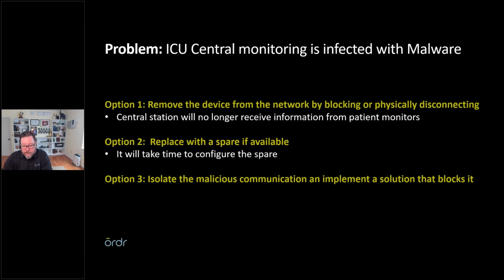Replace it with a spare if available, and that's a great solution, except I don't know if you've ever had to configure one of these devices. They're not an off-the-shelf device. They have to be configured to work in the environment they're in. That takes a significant amount of time, and that would be all downtime while that device was off the network. And then option 3 was what we talked about, which was to isolate the particular parts of the communication the device is doing that are malicious, and then implement the solution that blocks only those.